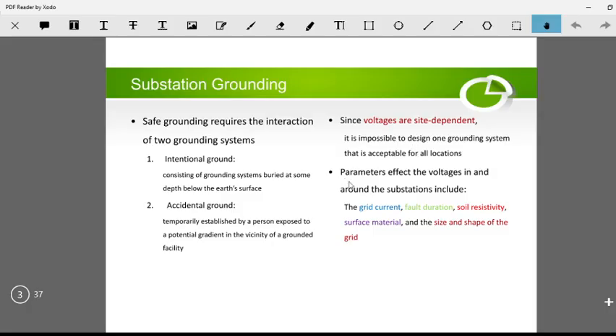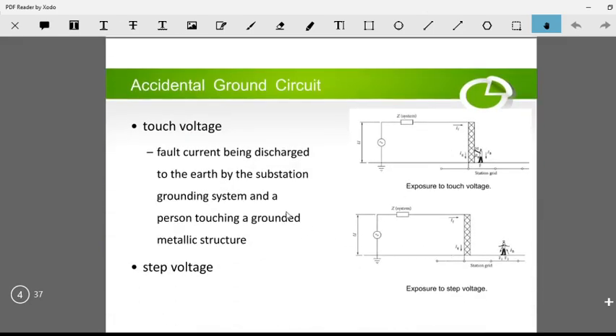These are some of the parameters that affect the voltage in the substation: grid current, fault duration, soil resistivity, surface material, and the size and shape of the grid. All of this matters for creating the grounding voltage and the voltage in and around the substation. When designing a substation, you have to consider all these parameters.